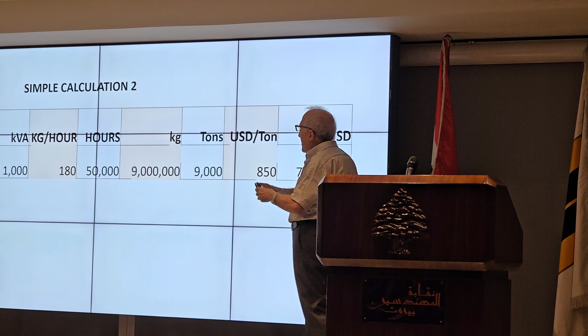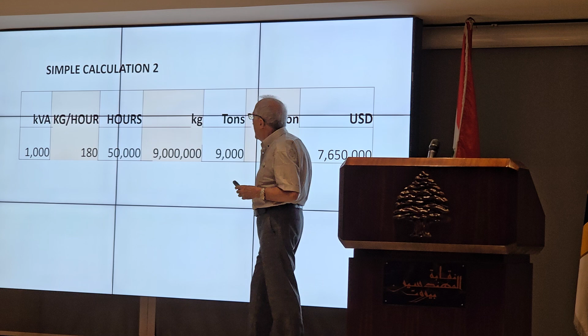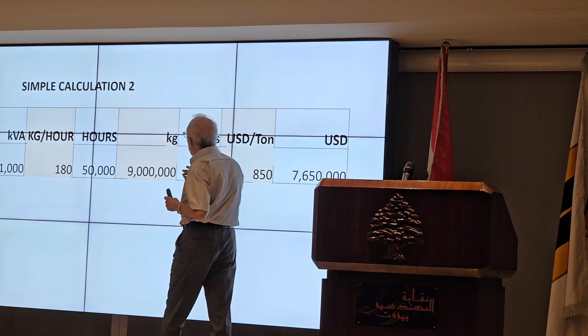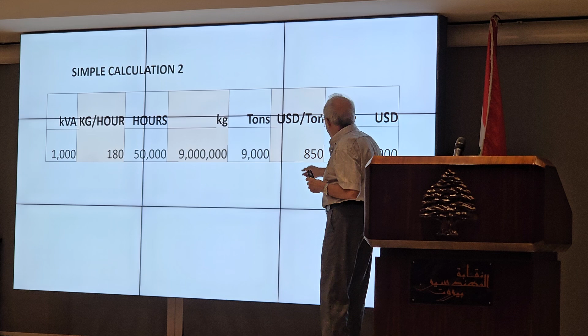Calculation number 2, very easy and straightforward. A 1,000 kVA generator will probably consume around 180 kilograms per hour of diesel. If it runs for 50,000 hours, this means it will consume about 9 million kilograms of diesel, or 9,000 tons, costing around 7,650,000 USD.